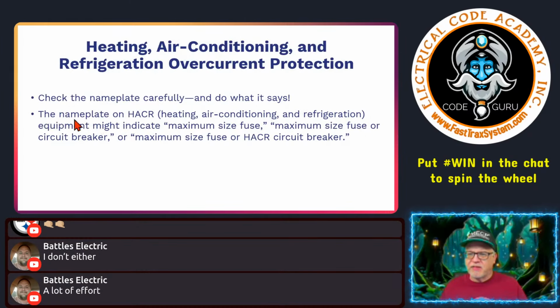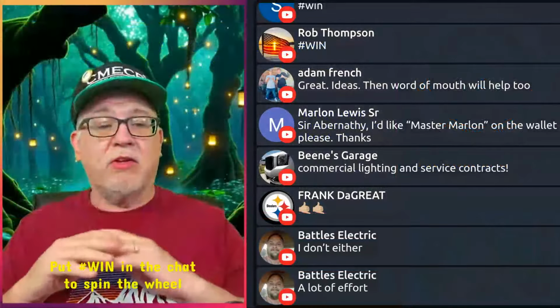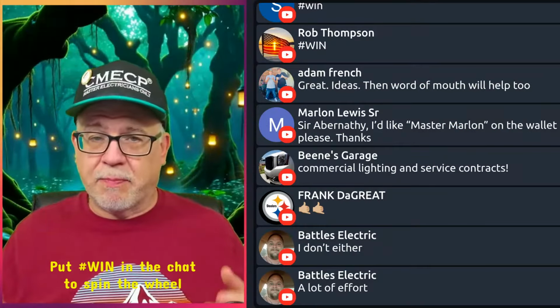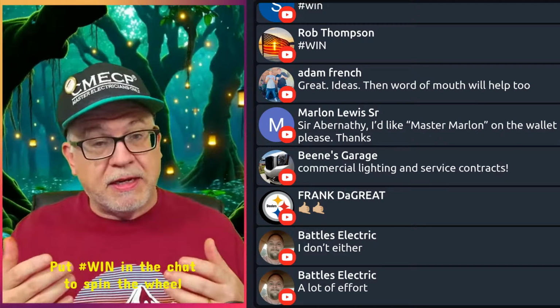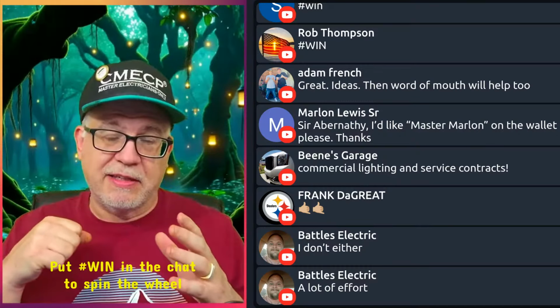It says a nameplate of an HACR, we call that hacker, says heating, air conditioning, and refrigeration equipment might indicate maximum fuse size, maximum fuse or circuit breaker, or maximum size fuse or HACR circuit breaker. I'm going to tell you right now, if you get a label that says maximum fuse size, if you're guys that are going out for older work and you're looking at it and it says maximum fuse size, folks, when it says that, you can only use a fuse in the system. Now, how do you get around that if the panel's got a circuit breaker? Well, typically all you require next to the unit is a disconnect.